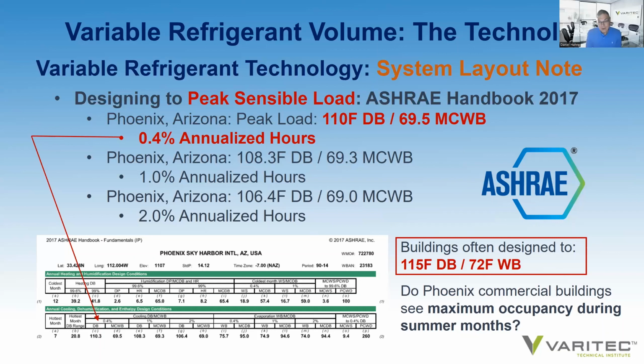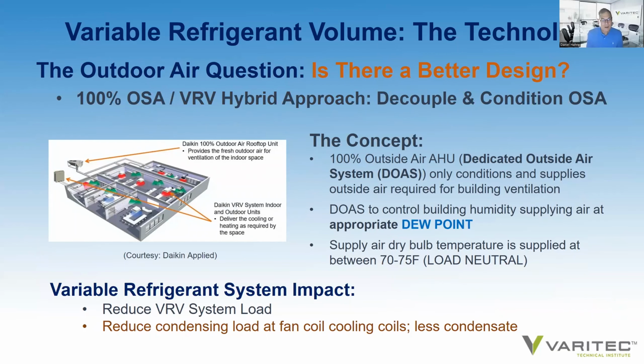And by the way, most engineers design to 115 degrees. So if you're upsizing condensers to meet that ambient condition, your 0.4% annualized hours becomes even less. So is there a better way to approach these types of systems? And the answer is, I think there is, and I think we should consider 100% outside air VRV a hybrid design, where we decouple and condition the outside air independent of the variable refrigerant system.